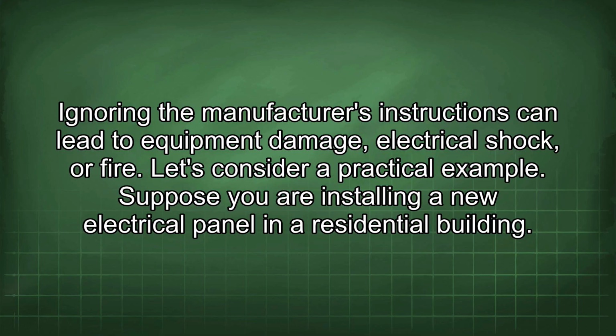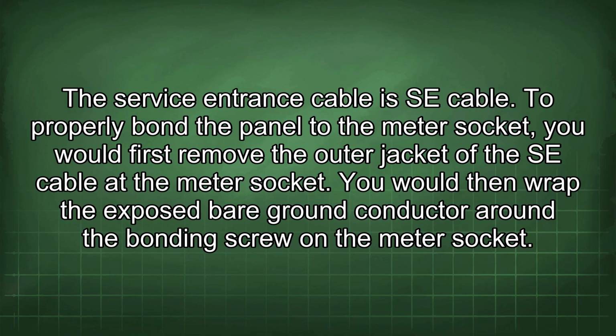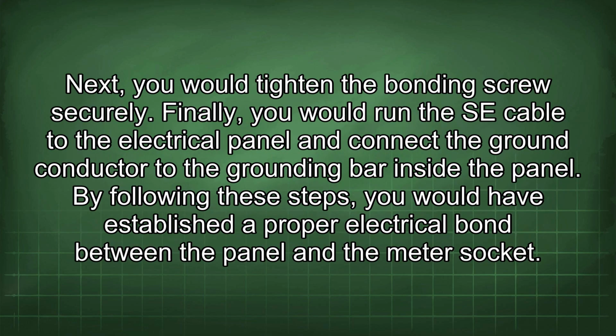Let's consider a practical example. Suppose you are installing a new electrical panel in a residential building. The service entrance cable is SE cable. To properly bond the panel to the meter socket, you would first remove the outer jacket of the SE cable at the meter socket. You would then wrap the exposed bare ground conductor around the bonding screw on the meter socket. Next, you would tighten the bonding screw securely.